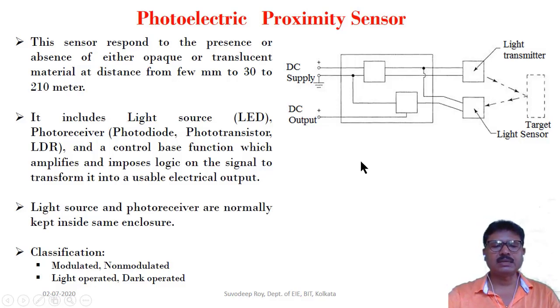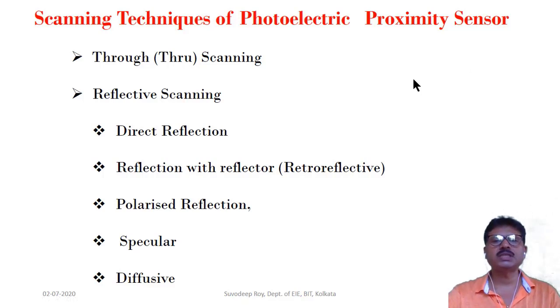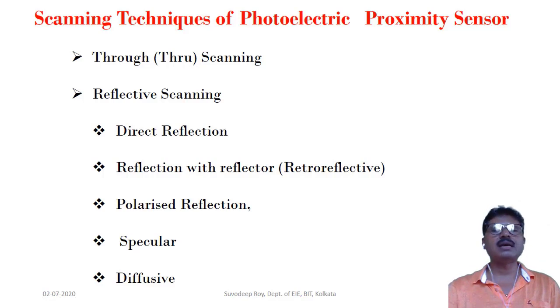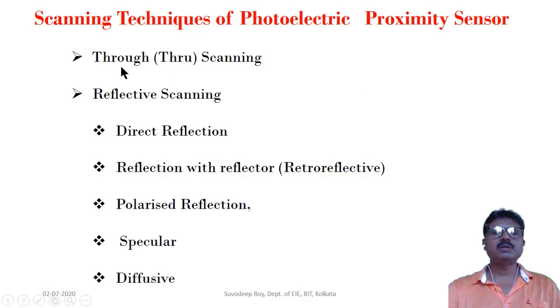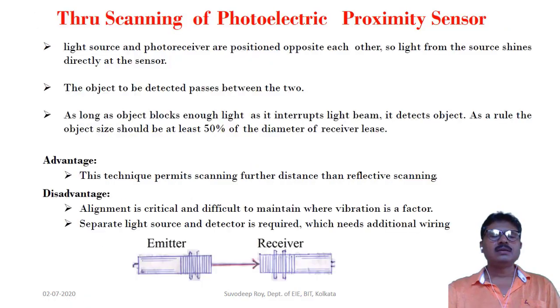A photoelectric proximity sensor has different installation types — these are the scanning techniques, which mainly depend on installation: how the sensors and receivers are installed in a plant. There are two main types: through scanning and reflective scanning. Reflective scanning is further divided into: direct reflection, reflection with reflector (also called retroreflective), polarized reflection, specular, and diffusive.